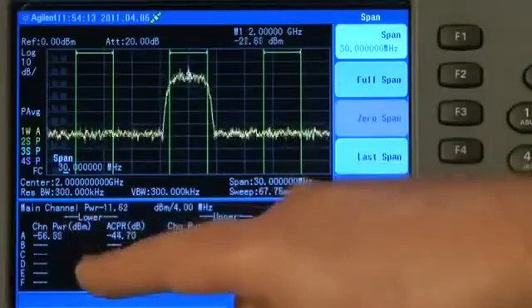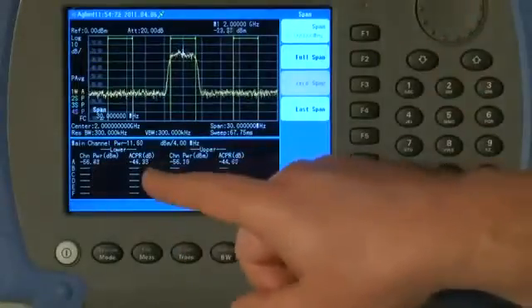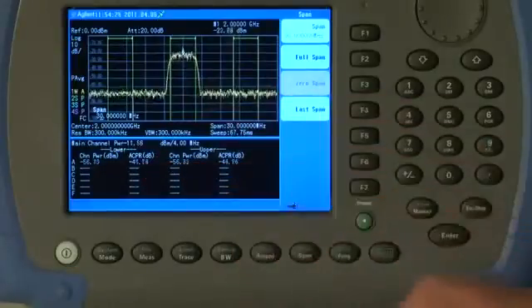And we do not have to just do it with two adjacent channels. As you can see here, we can have up to six adjacent channels on either side of the main channel. And in real time, the analyzer will tell us the absolute values and the relative values relative to the main channel power.